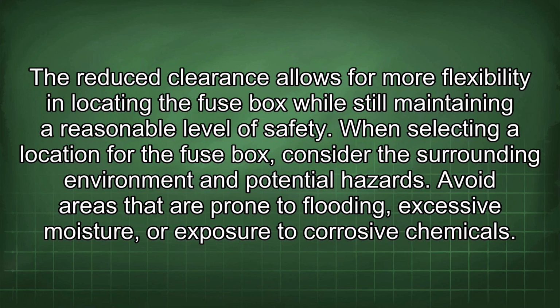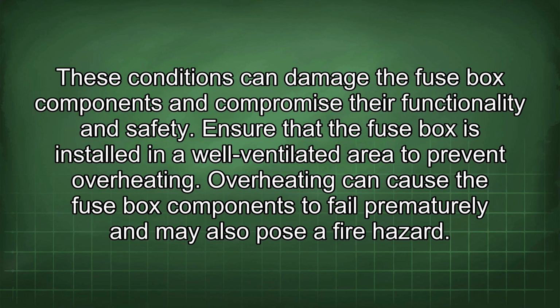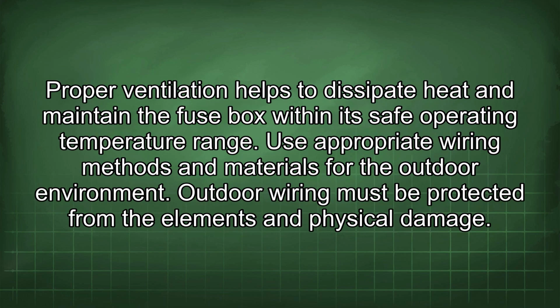When selecting a location for the fuse box, consider the surrounding environment and potential hazards. Avoid areas that are prone to flooding, excessive moisture, or exposure to corrosive chemicals. These conditions can damage the fuse box components and compromise their functionality and safety. Ensure that the fuse box is installed in a well-ventilated area to prevent overheating. Overheating can cause the fuse box components to fail prematurely and may also pose a fire hazard. Proper ventilation helps to dissipate heat and maintain the fuse box within its safe operating temperature range.